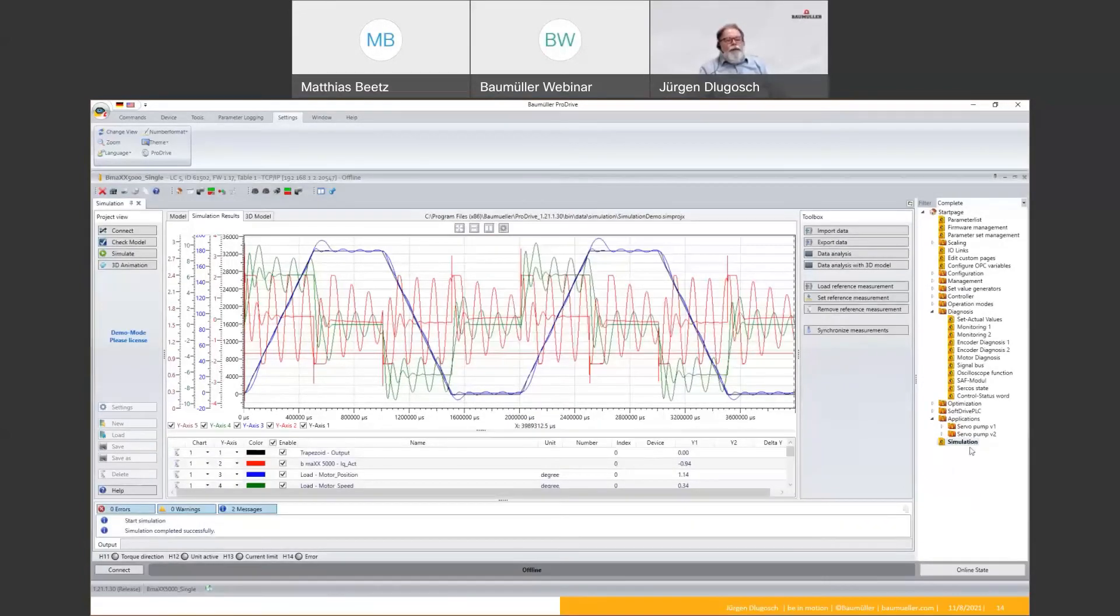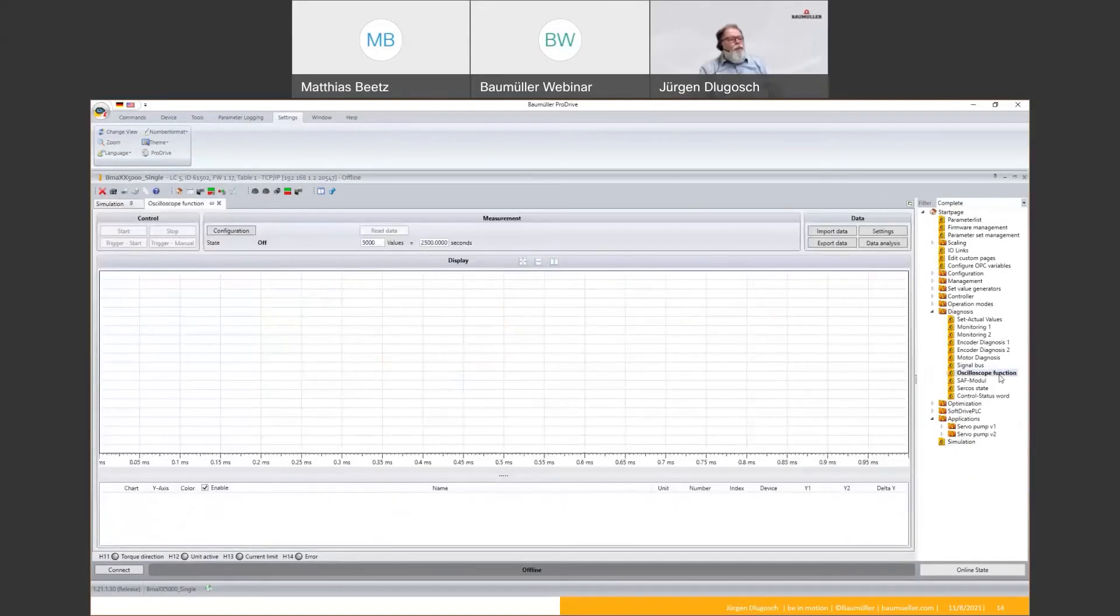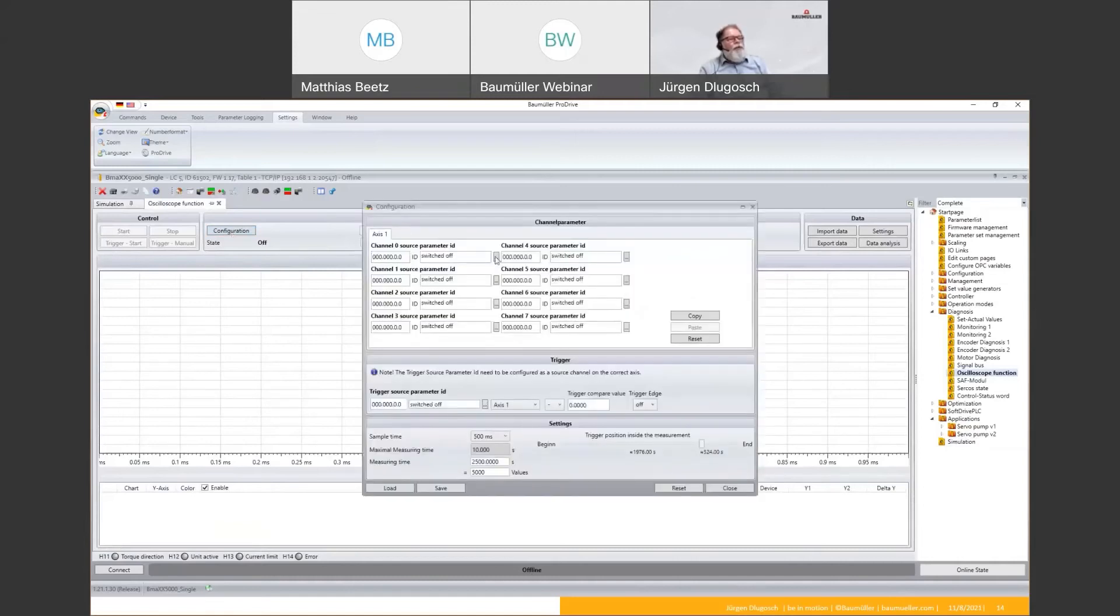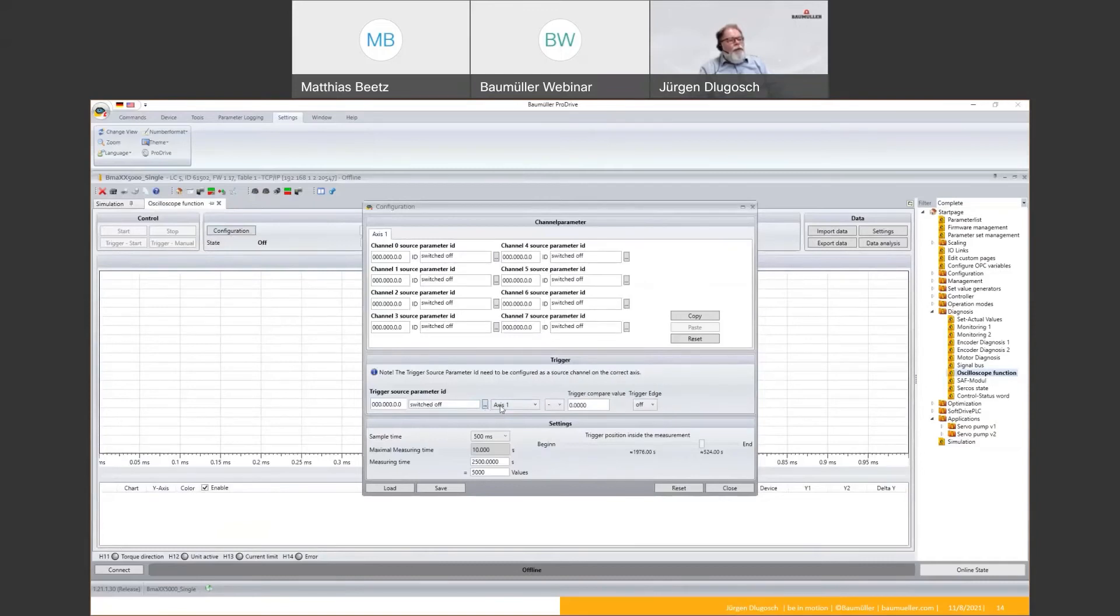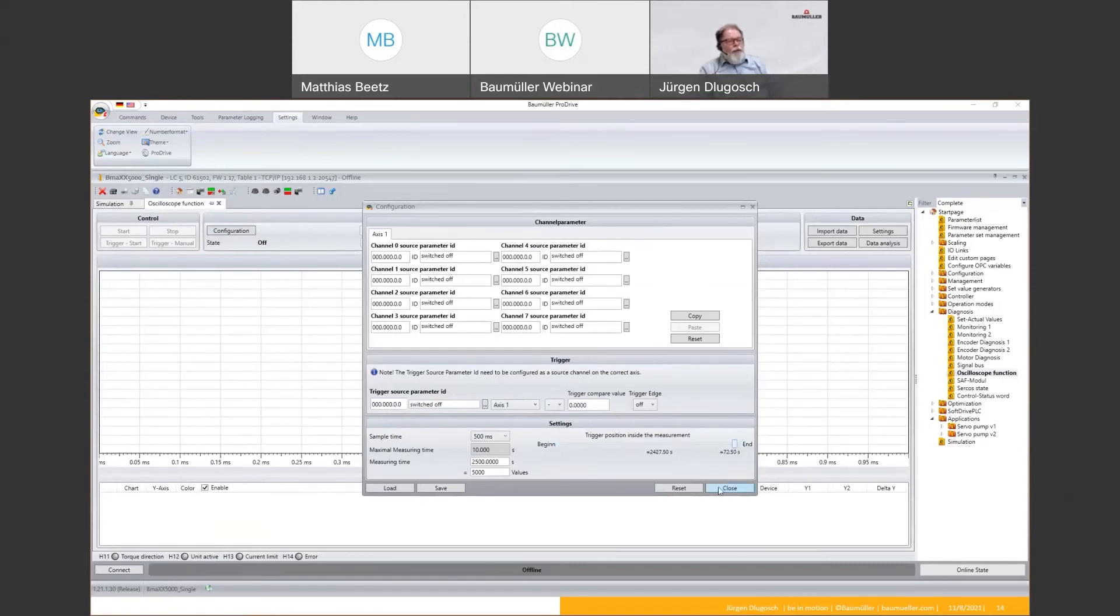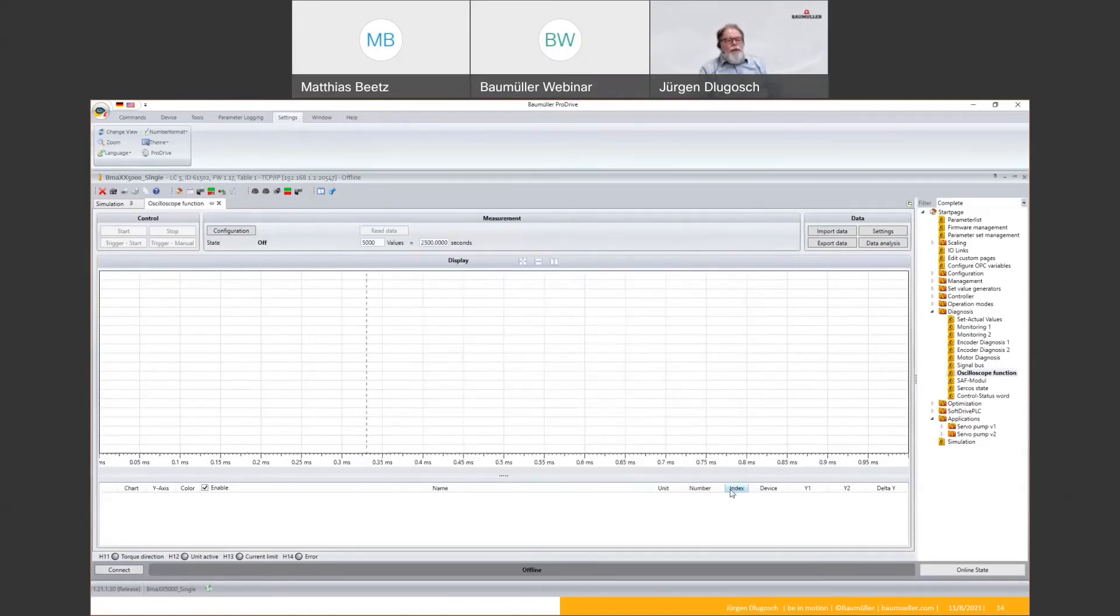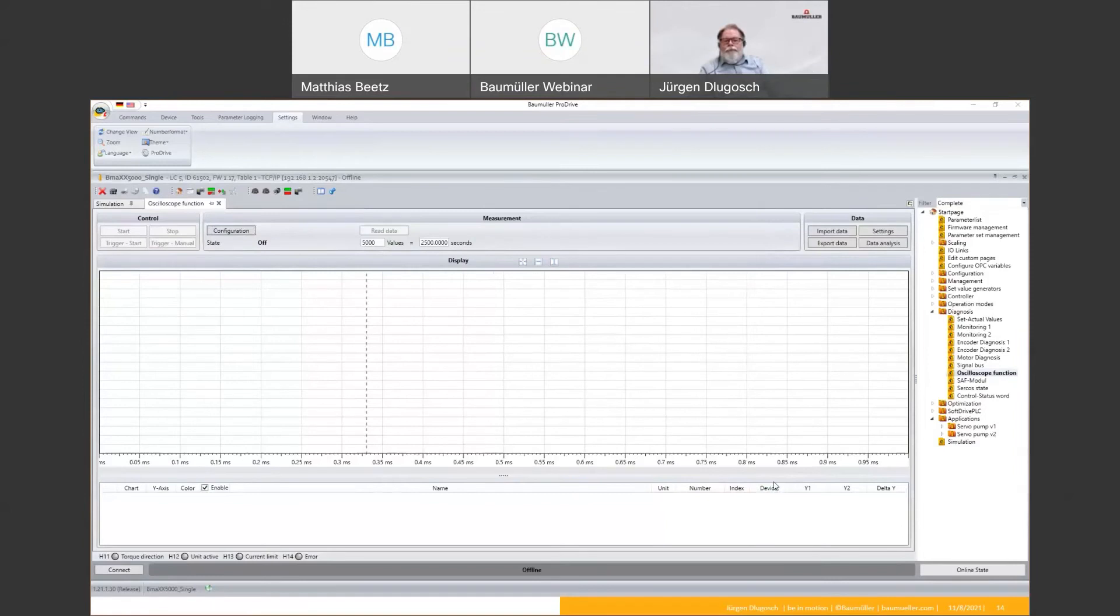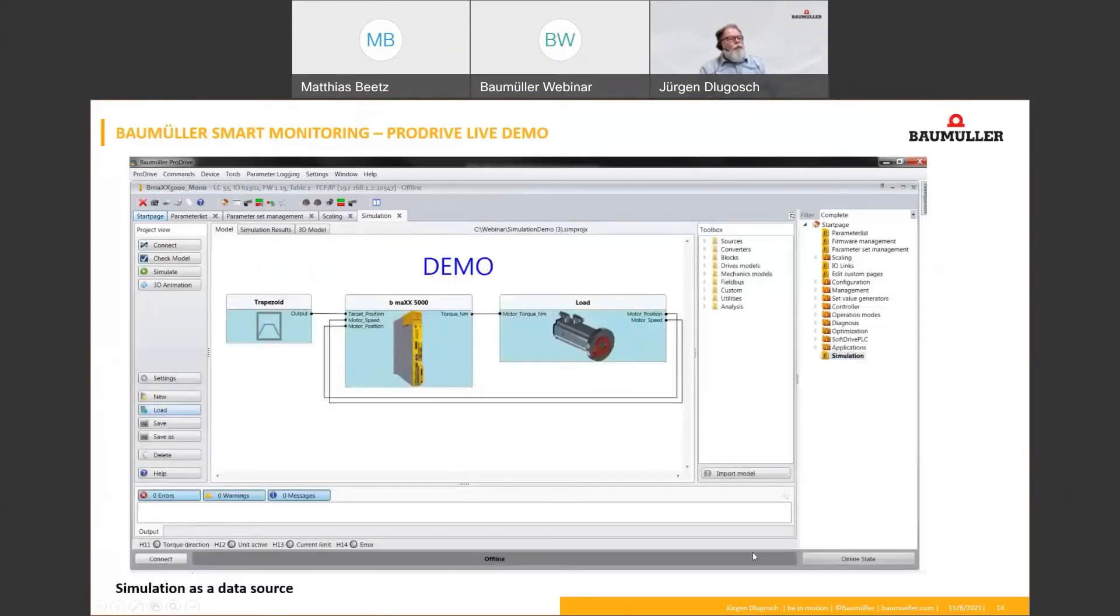Last thing I want to show is a ring buffer, the ring buffer oscilloscope function. Here I will show only the possibility for the configuration of it. We have here also the possibility to use eight channels. We can select a trigger source. We can make some logical combination on the trigger. And what I explained before, we have here the pre-trigger function to see what happens before. We can adjust from a very small time span up to maximum time. This is a very important thing in case of error diagnostics.